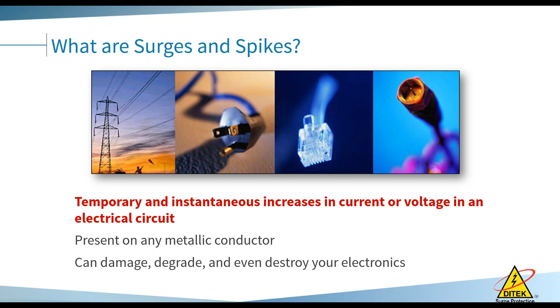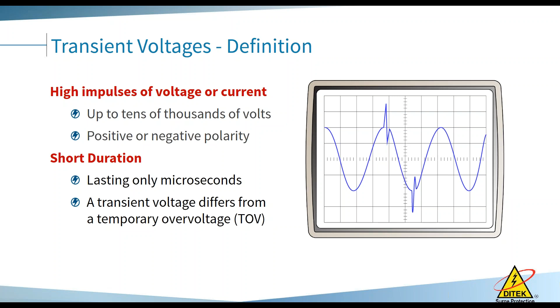Let's talk about the different types of surges. Transient voltage surges have two definitions: a high impulse of voltage or current, which can be tens of thousands of volts in positive or negative polarity, of short duration, only microseconds. These are different from temporary overvoltage. A transient voltage can be positive or negative and lasts microseconds, while temporary overvoltage is positive and can last seconds, even minutes or hours. So totally different events.